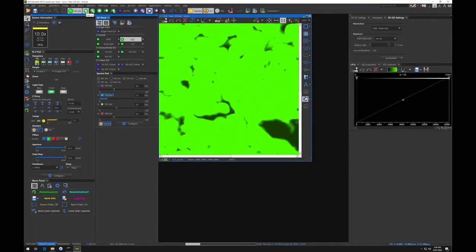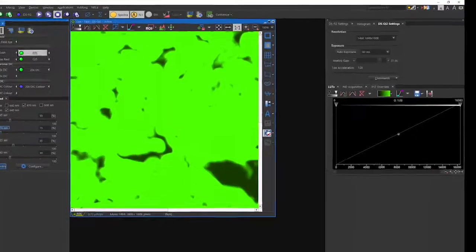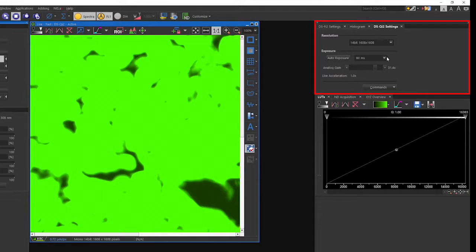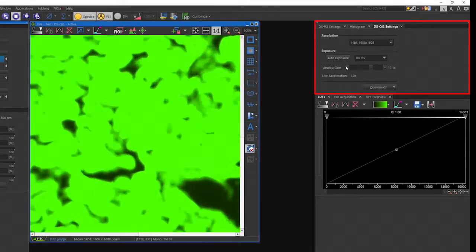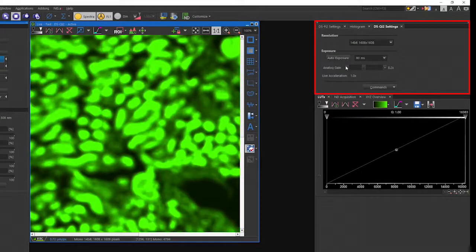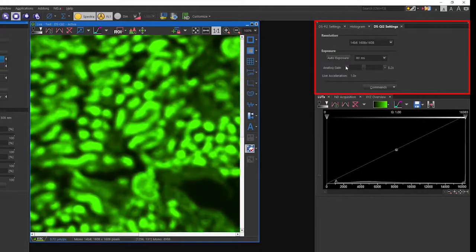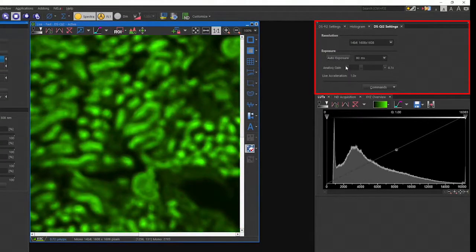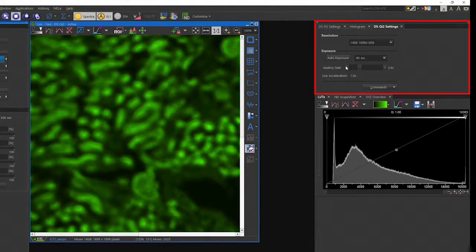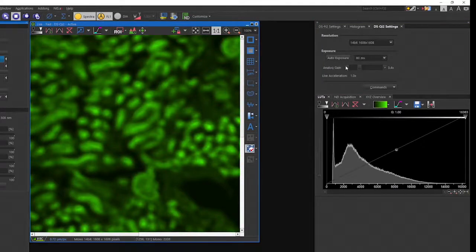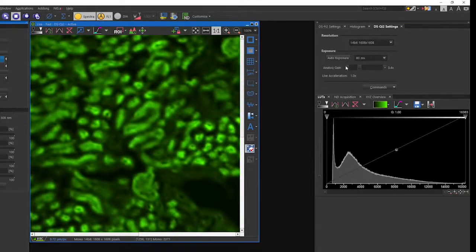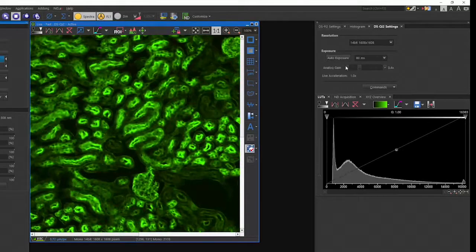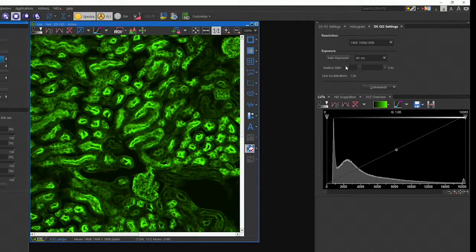This sample is very bright. The Qi2 camera has a default setting very high in gain, useful with dim samples. You can lower or raise the gain using the slider. You can also adjust the exposure time on the camera or the LED power for the 470nm LED to optimize the image.